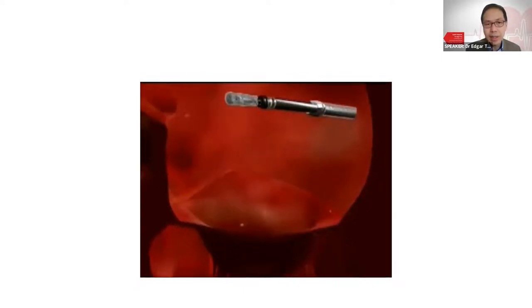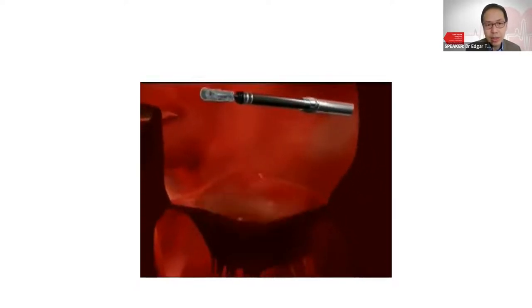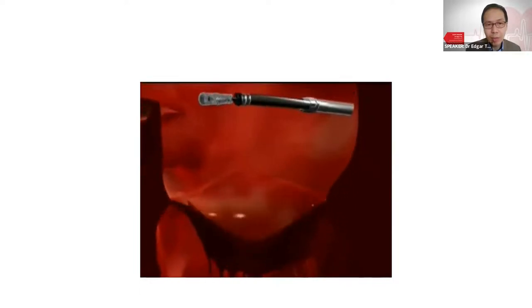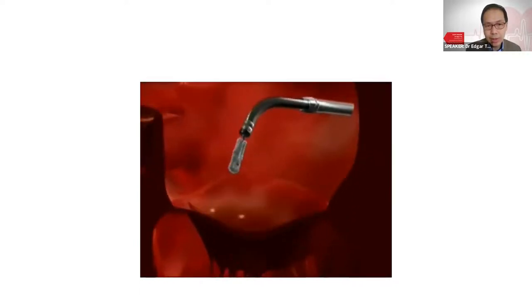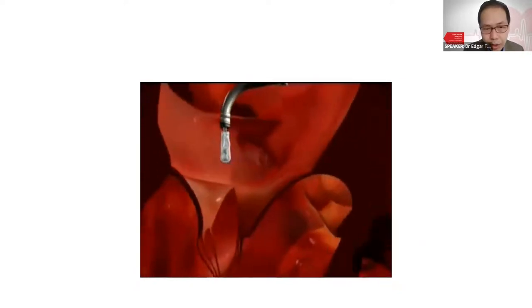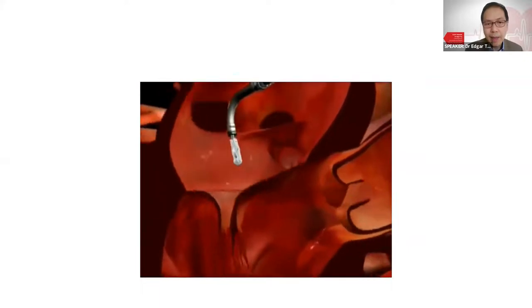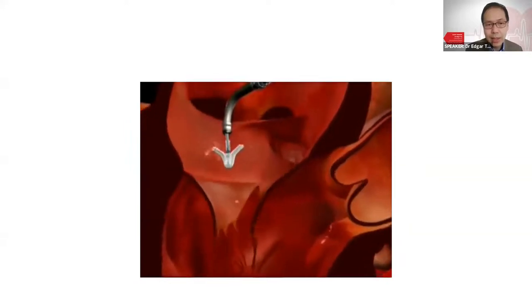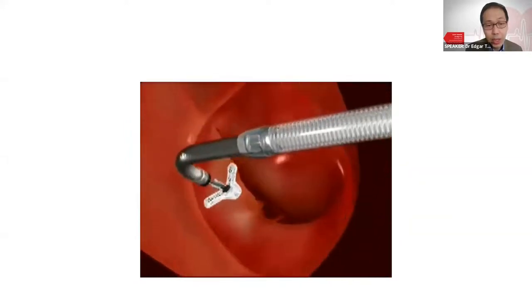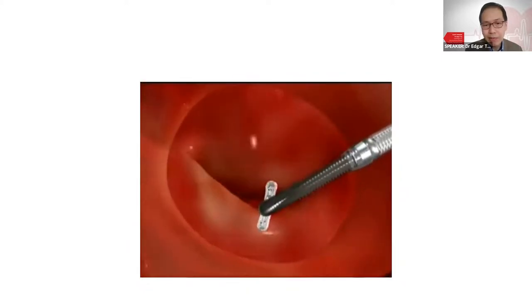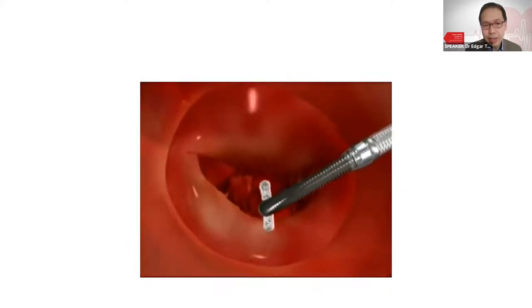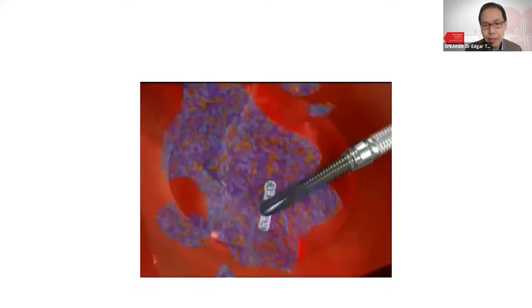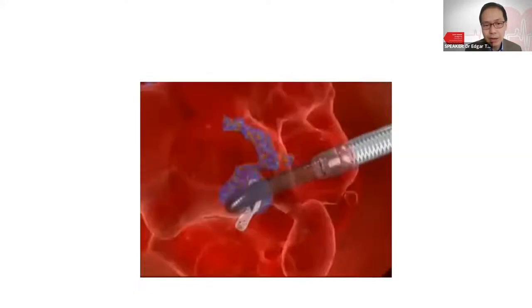The mitral clip is now currently closed. So you see it almost like a kind of an oblong rectangular structure. And it's flexible and it's controlled out of the patient's body. It allows a variety of flexion and extension motions, medial and lateral movements. And it can be opened, its wings can be opened. And here you're seeing the valve from the atrial end. You can see then quickly the blue jet of blood is regurgitating back into the left atrium.